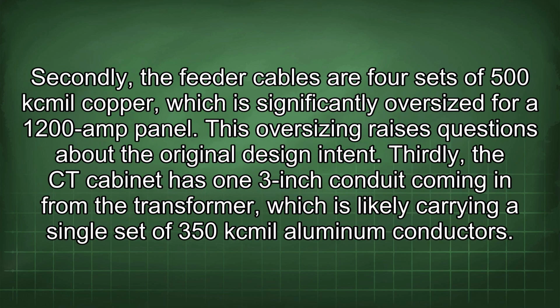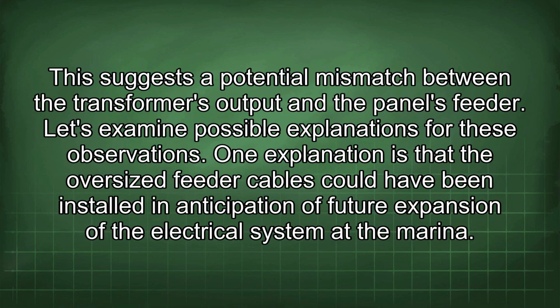Secondly, the feeder cables are 4 sets of 500 kcmil copper, which is significantly oversized for a 1200 amp panel. This oversizing raises questions about the original design intent. Thirdly, the CT cabinet has one 3-inch conduit coming in from the transformer, which is likely carrying a single set of 350 kcmil aluminum conductors. This suggests a potential mismatch between the transformer's output and the panel's feeder. Let's examine possible explanations for these observations.